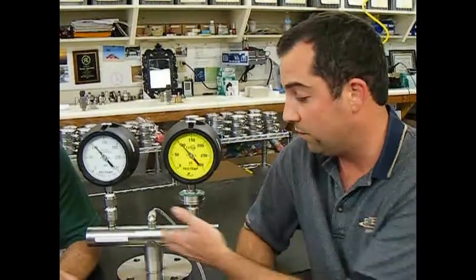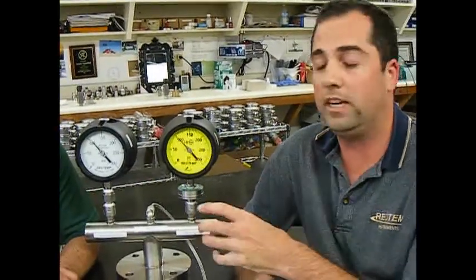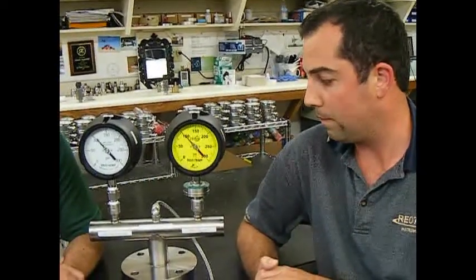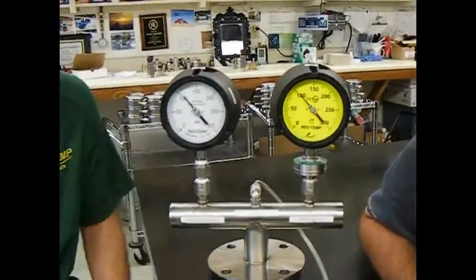In this jig we have a fully enclosed water line, so we're just using simple water. We're going to run a sawtooth wave type of pulsation at about 200 to 300 cycles per minute in order to simulate the effect of pulsation on these gauges. Now we'll go ahead and turn on this unit and you'll be able to see the effects of pulsation for real.